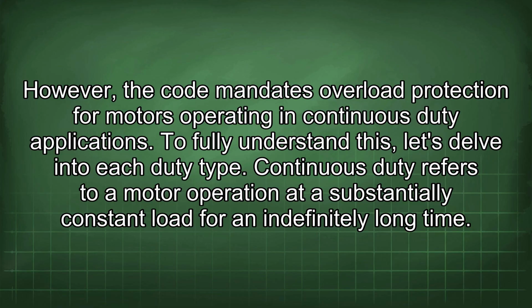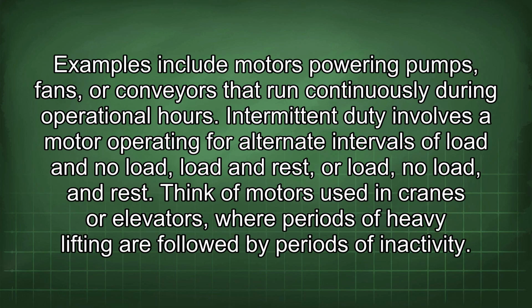Continuous duty refers to a motor operation at a substantially constant load for an indefinitely long time. Examples include motors powering pumps, fans, or conveyors that run continuously during operational hours. Intermittent duty involves a motor operating for alternate intervals of load and no load, load and rest, or load, no load, and rest.